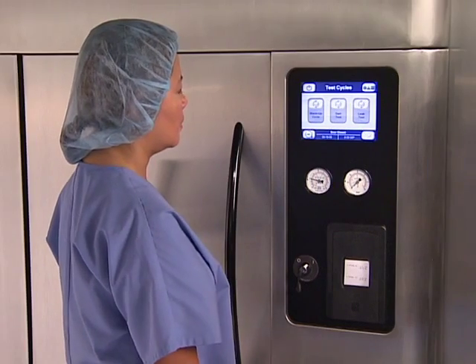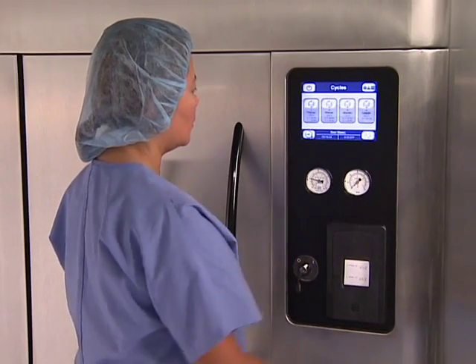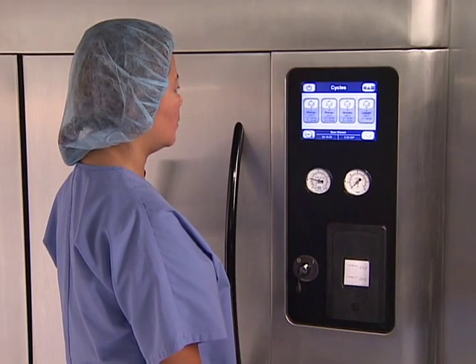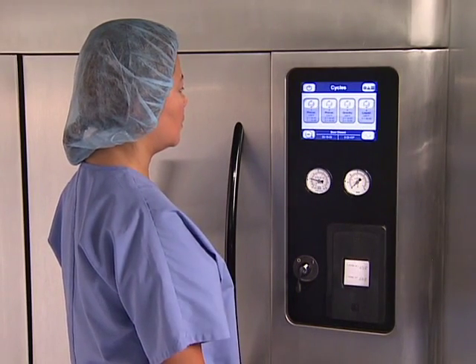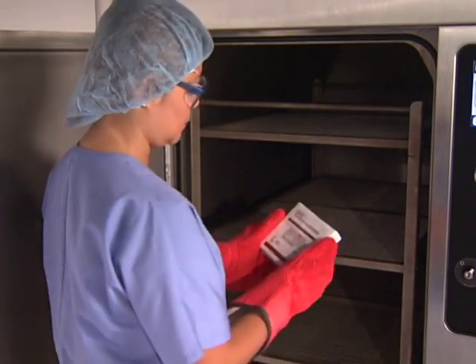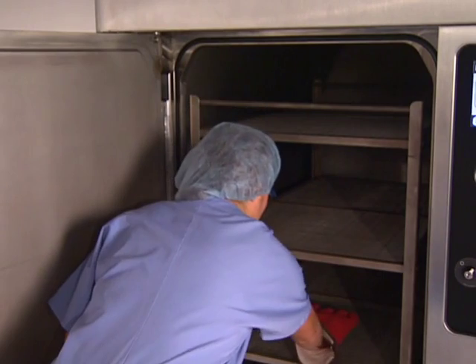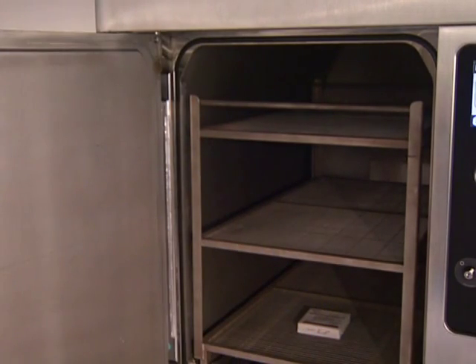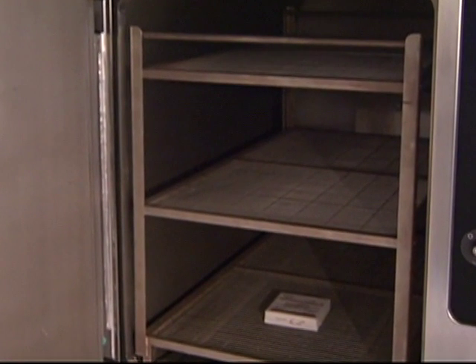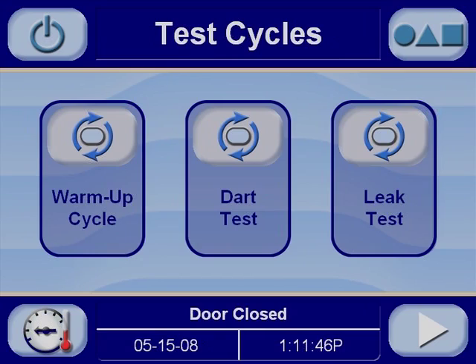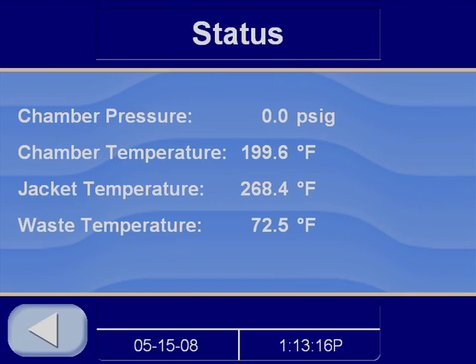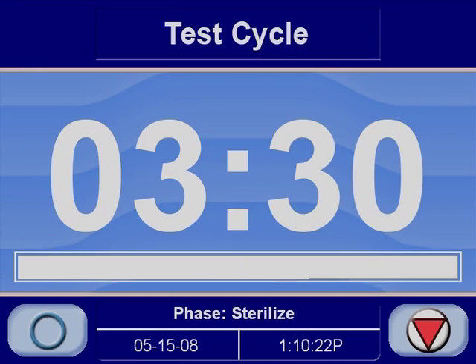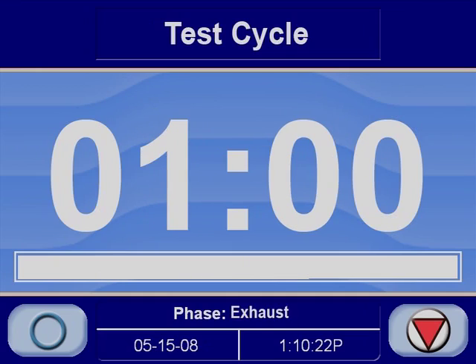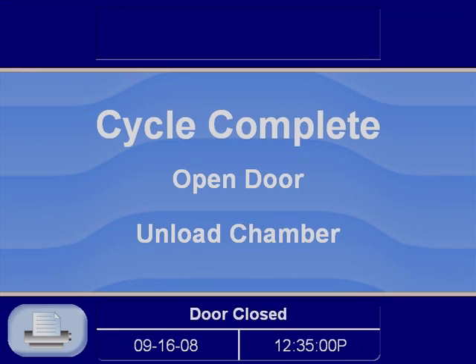To initiate a warm-up cycle, press the right arrow on the cycle screen until the test cycle screen appears. Press the warm-up cycle button. Once the warm-up cycle is finished, place a DART test or properly prepared Bowie-Dick test pack or commercially available test pack on the lowest rack of the sterilizer loading cart. Make sure the test pack is positioned above the chamber drain. Press the DART test button to begin the cycle. The sterilizer temperature will reach 270 degrees Fahrenheit. After 3.5 minutes of sterilize time and 1 minute of dry time, the test cycle is complete.